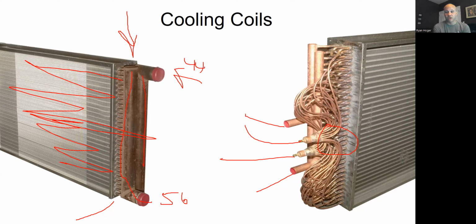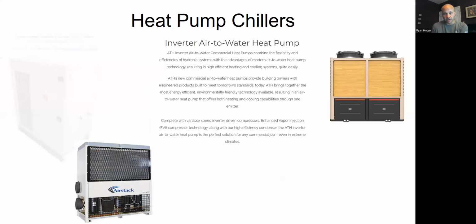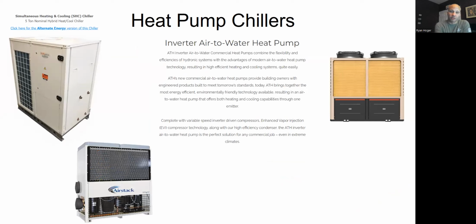More likely is you have one chiller feeding 30 air handlers, or you have a chiller plant with 3, 4, 5 chillers feeding a bunch of air handlers or small fan coils or whatnot. So then your decision process is a little bit different. You will not be converting it over zone by zone. You'll be converting the whole building over at one time. So we have several different options on what we can do in this regard, and it depends on the kind of building and what we're doing.